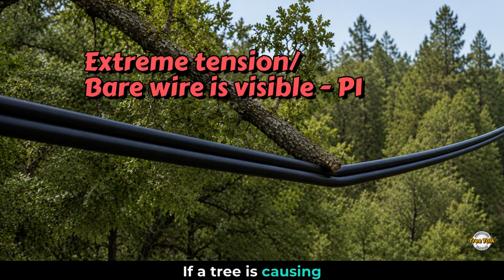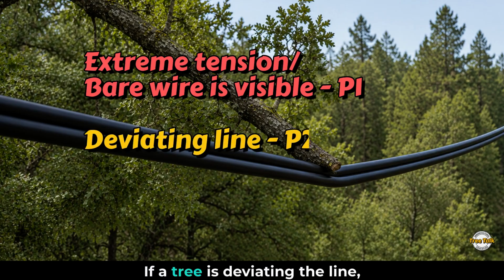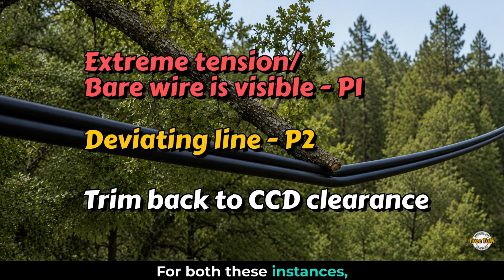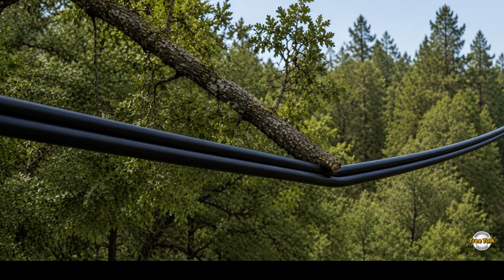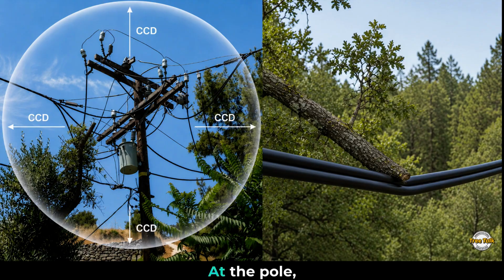If a tree is causing extreme tension, or bare wire is showing through the covered insulation, then that's a P1. If a tree is deviating the line, then that's a P2. For both these instances, trim the vegetation back to CCD clearance. So the question changes depending on where you are. At the pole, ask, will the vegetation break CCD clearance? Along the span, ask, is this rubbing or putting weight on the cable?